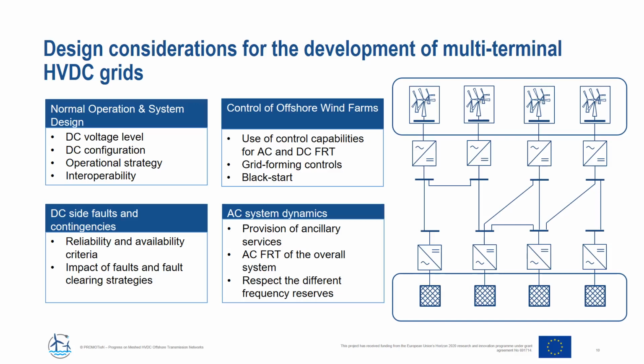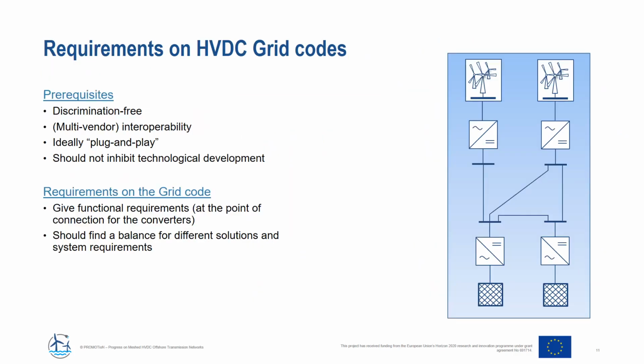So coming from this, let's see what a DC grid code would require. In general, a DC grid code should be discrimination-free to ensure interoperability between the different components, but also between different vendors connected to the system. Ideally, it would be plug and play, and it should not inhibit the technological development, because in general, the HVDC technology is still under development. So requirements on the grid code are that it gives functional requirements at the point of connection for the converters, AC point of connection and DC point of connection, and it should find a balance for different solutions and the system requirements.